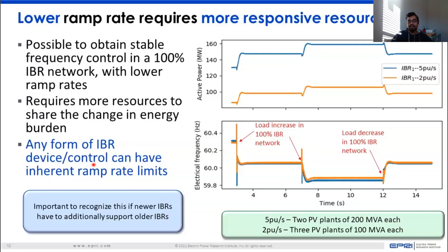So as an interim summary: the increased rate of change of frequency, the way we have it, can cause misoperation of UFLS relays, or cause UFLS relays to be hit. But the draft P2800 standard has tremendous potential to provide benefit from a frequency response perspective. We need to be cognizant of things like ramp rate and the dynamics of the source behind the inverter, and also the number of resources we're calling upon to provide this service, while ensuring the inverter-based resource provides the service as fast as technically feasible without causing instability. So it doesn't mean you have to have a fast ramp rate if it causes subsequent instability—that needs to be considered.